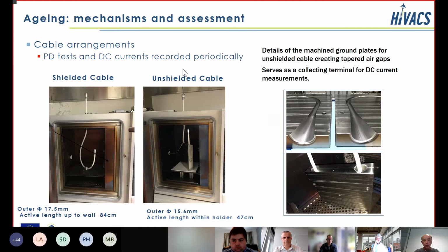We have a different arrangement for shielded and unshielded cables due to the way of collecting current or detecting PD. For the shielded cables, we treated just the end of the shield to try to avoid the discharge at the end. So we have one end inside the oven and the other outside the oven, and we collect DC current through the ground outside for the DC current measurements.